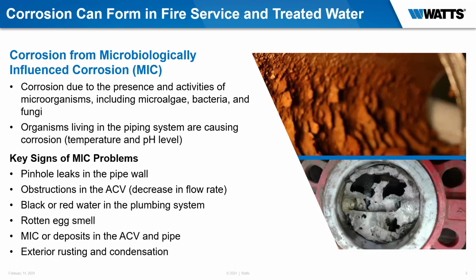When somebody takes the pipe apart, you go, whoa, that smells awful. Then all of a sudden that black water comes out of the sprinkler system, and if there's a rug there, it'll stain it. It's nasty, and that's all the result of MIC corrosion going on in the system.